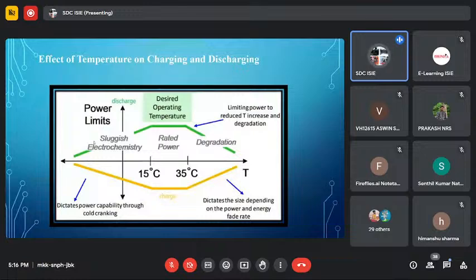So if the temperature goes below 15 degrees Celsius, that electrolyte will get solidified. And if it solidifies, it will be very hard to move those electrons and lithium ions. So we need to keep that electrolyte in liquid or semi-liquid form. If it solidifies, it will go into sluggish electrochemistry and reduce the rated power capacity.